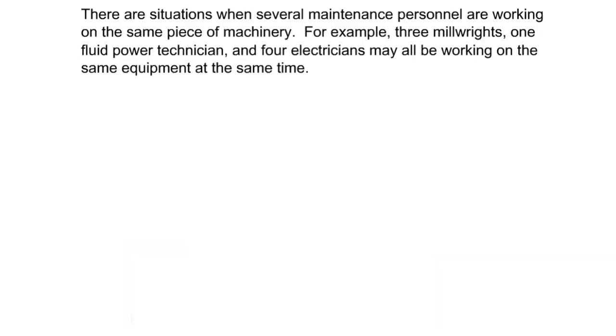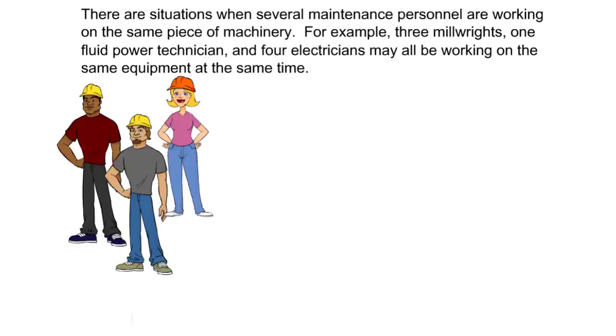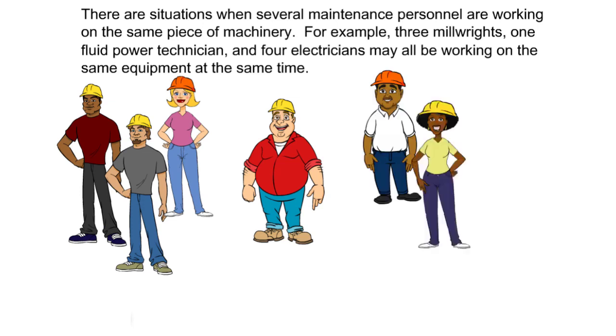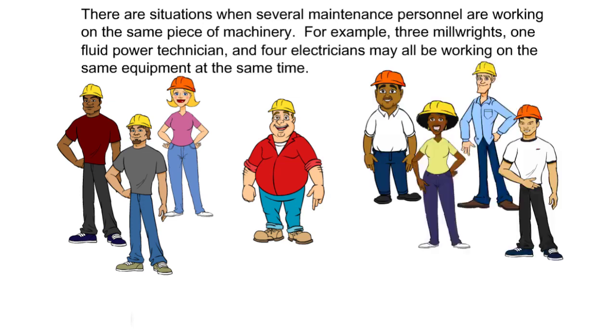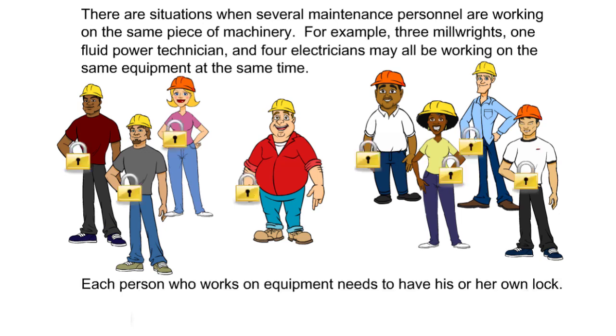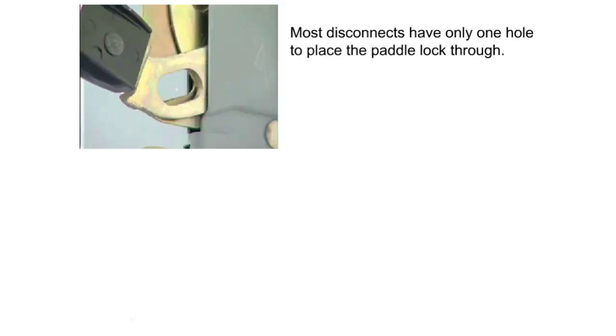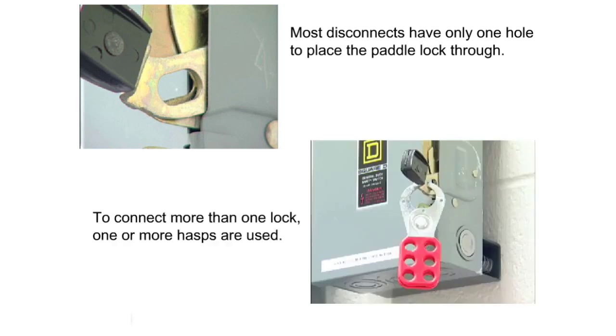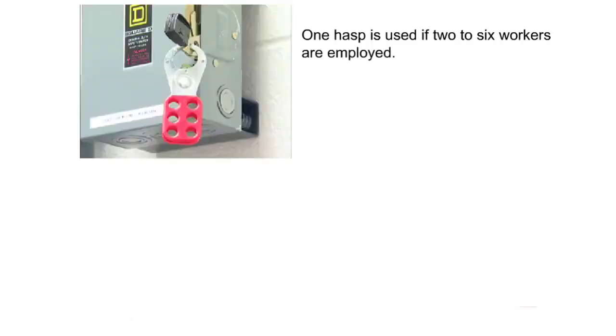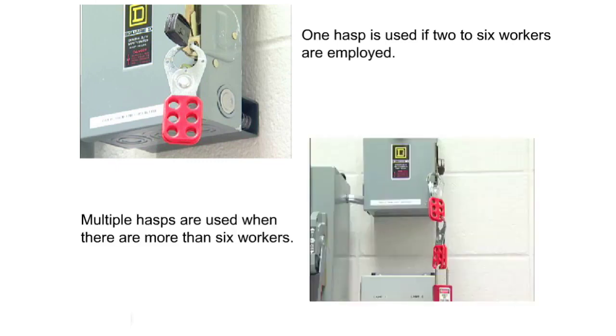There are situations when several maintenance personnel are working on the same piece of machinery. For example, 3 millwrights, 1 fluid power technician, and 4 electricians may all be working on the same equipment at the same time. Each person who works on equipment needs to have his or her own lock. Most disconnects have only one hole to place the padlock through. To connect more than one lock, 1 or more hasps are used. 1 hasp is used if 2 to 6 workers are employed. Multiple hasps are used when there are more than 6 workers.